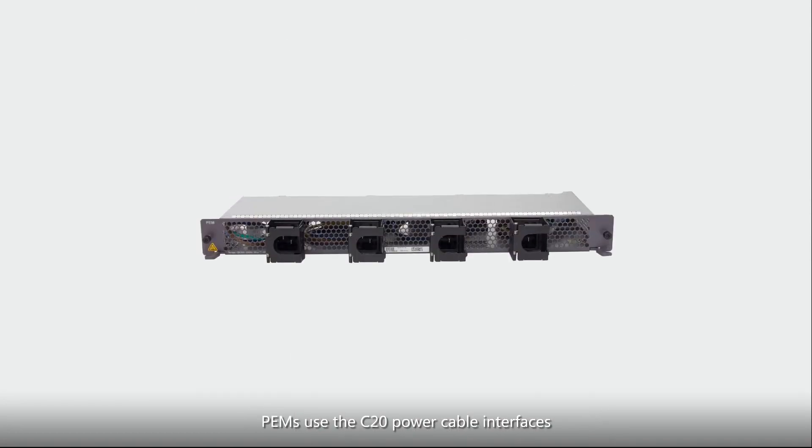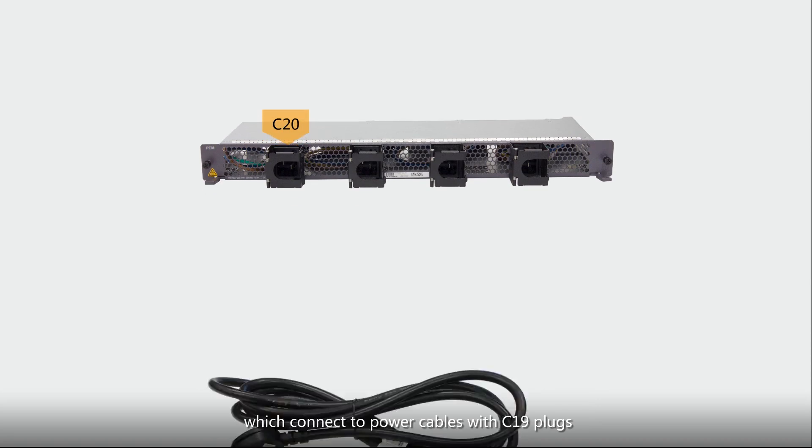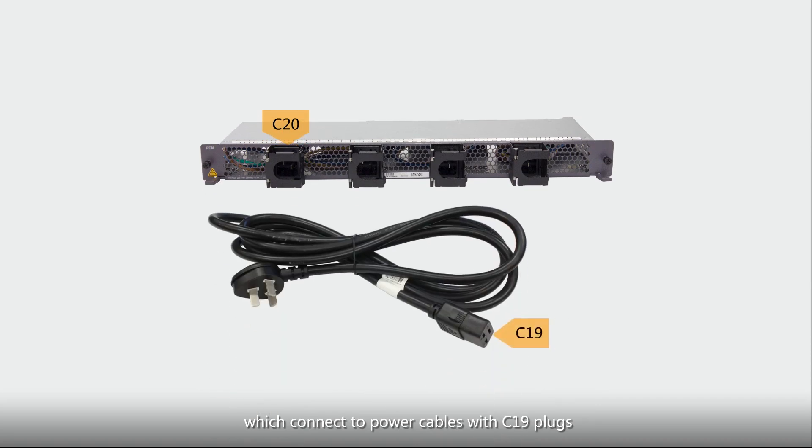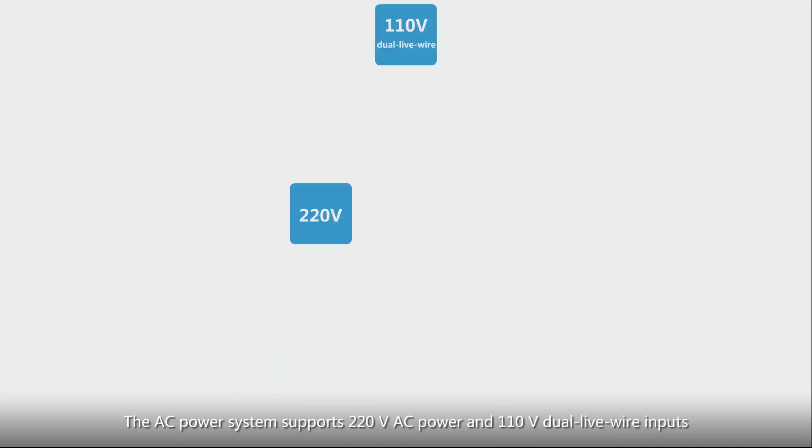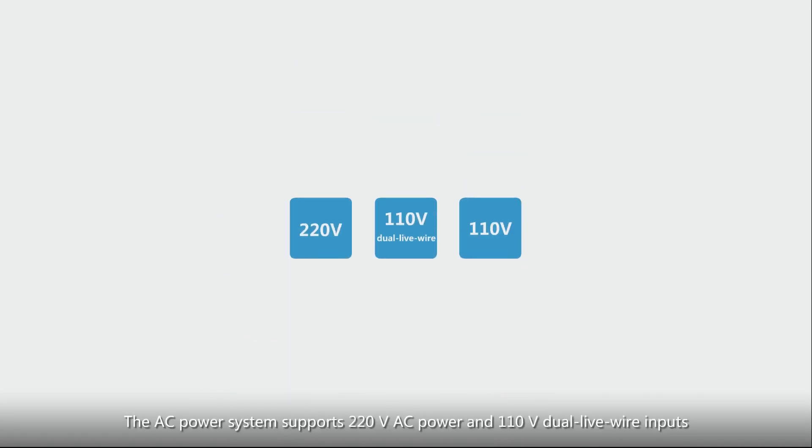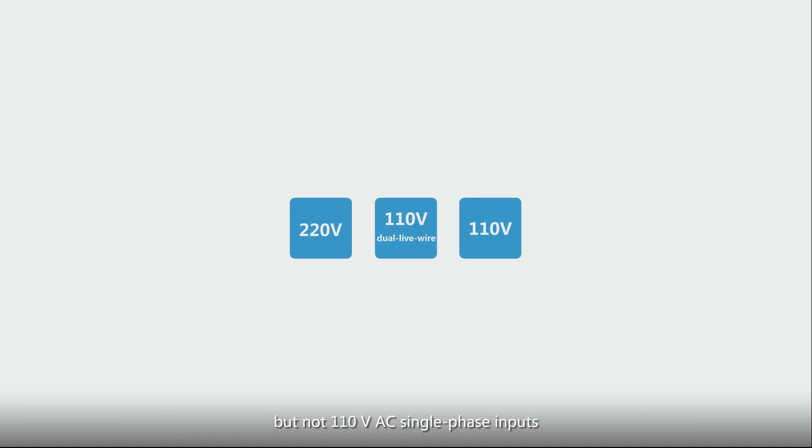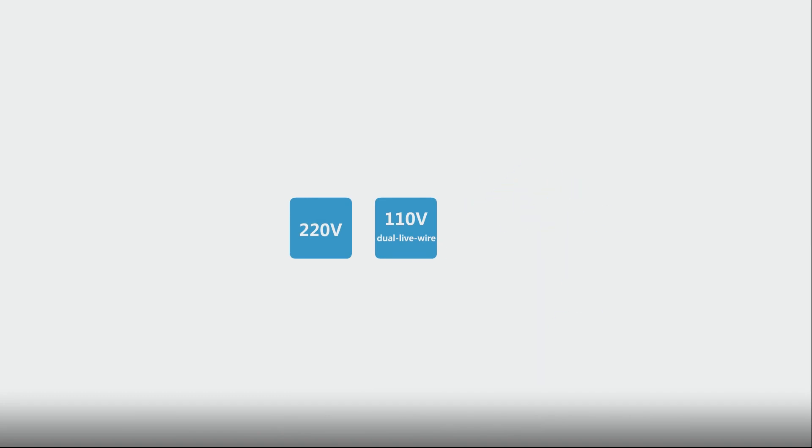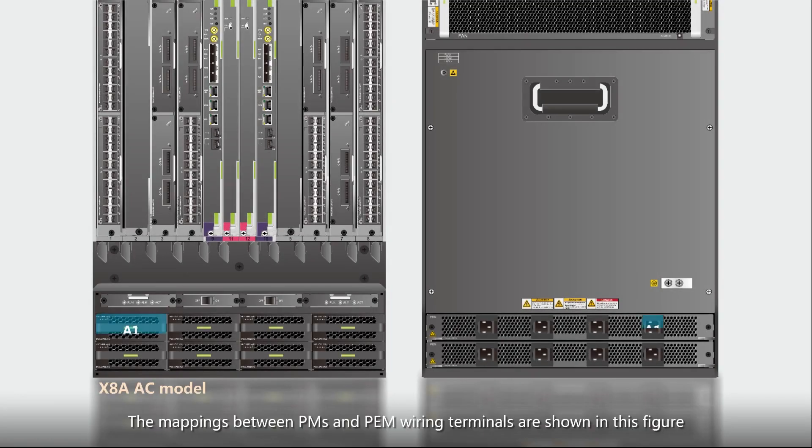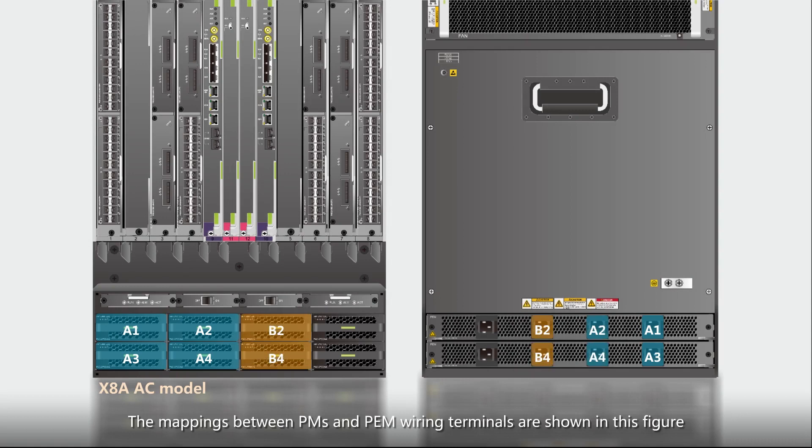PEMs use the C20 power cable interfaces, which connect to power cables with C19 plugs. The AC power system supports 220V AC power and 110V dual live wire inputs but not 110V AC single phase inputs. The mappings between PMs and PEM wiring terminals are shown in this figure.